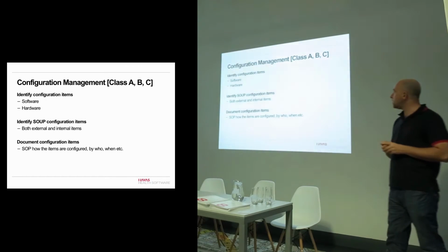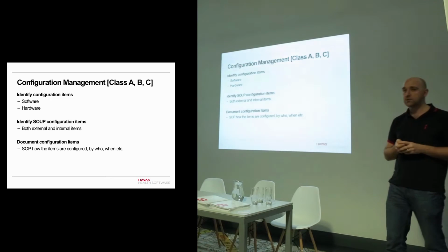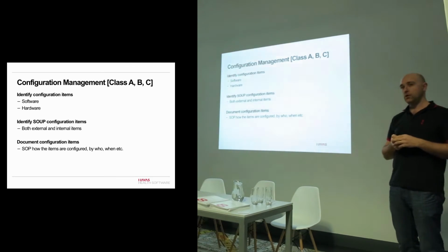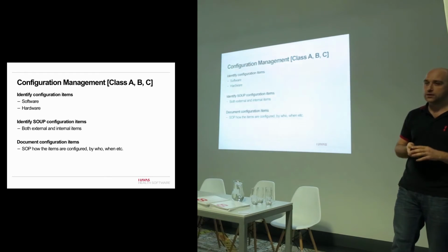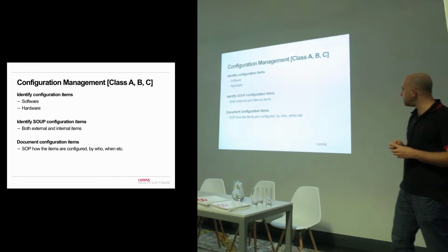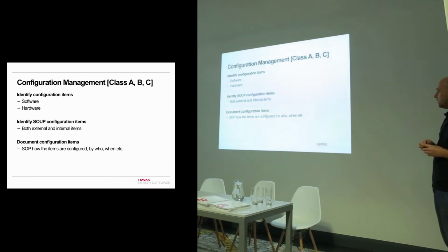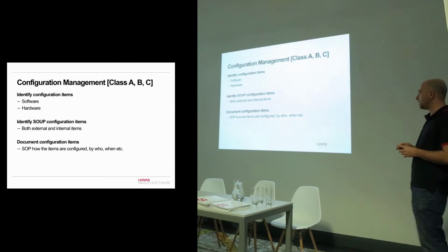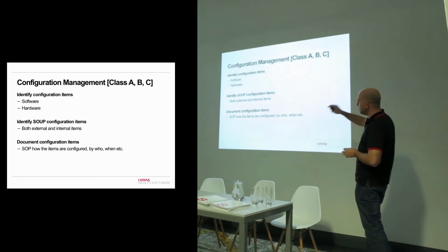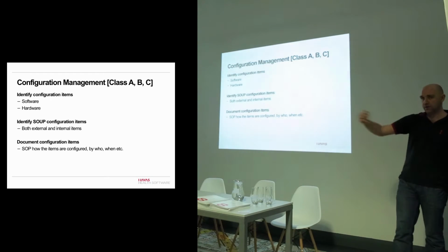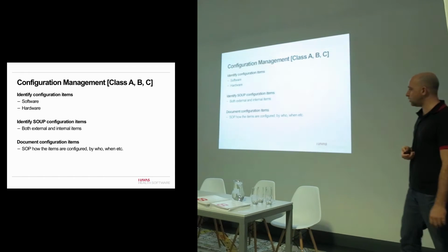The other thing you need as well is configuration management. The reason why you need configuration management is it's really important. Again, in the mobile application sense, deploying it to a phone, what operating system is on that phone, how are you deploying it? If you're deploying to Android, for example, how are you controlling the multitude of Android versions that you will potentially target? In doing so, are you deploying it in exactly the same way in every instance, or if that's changing, how is that changing? Again, in terms of configuration, you really need to document how it's configured. That's really important as well. How am I configuring this? You need to show that, so you can prove those things.